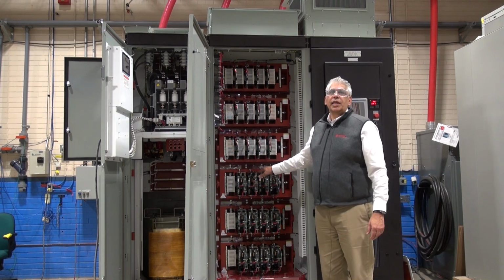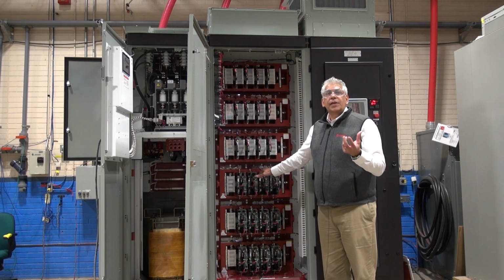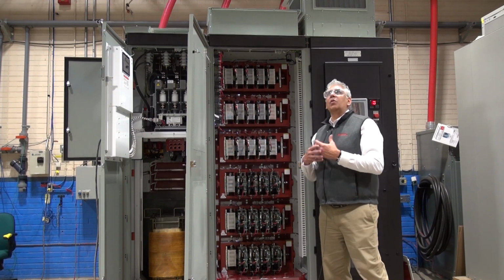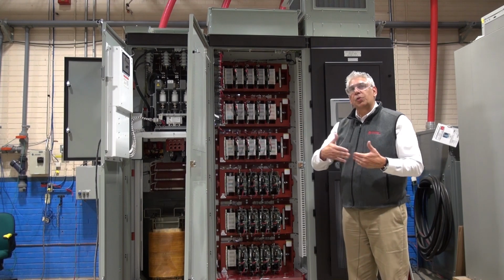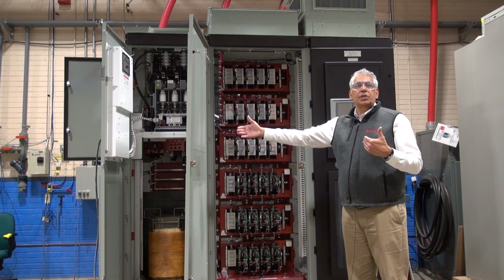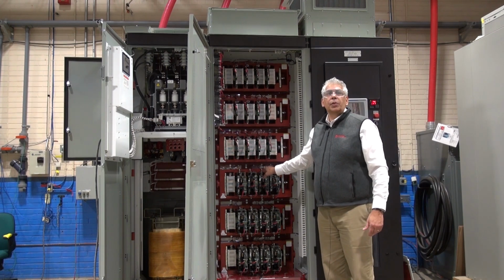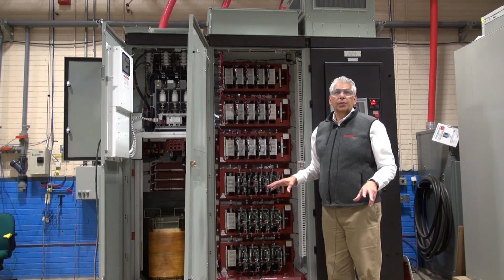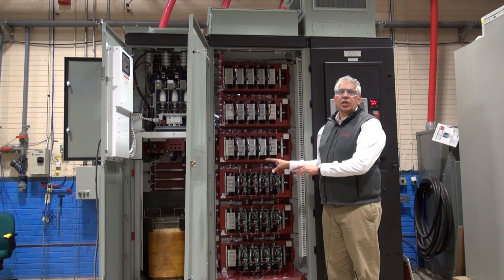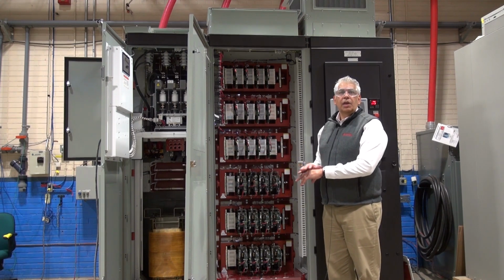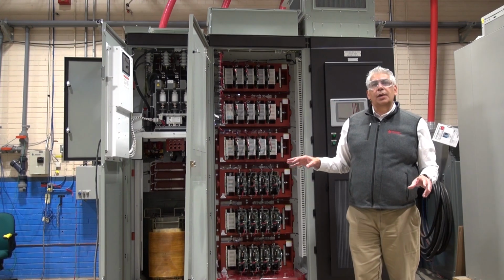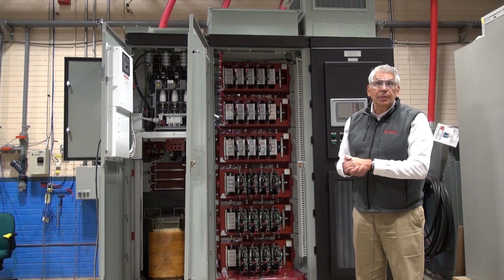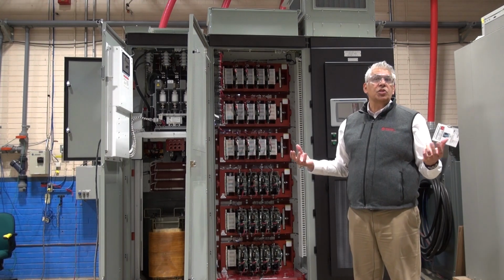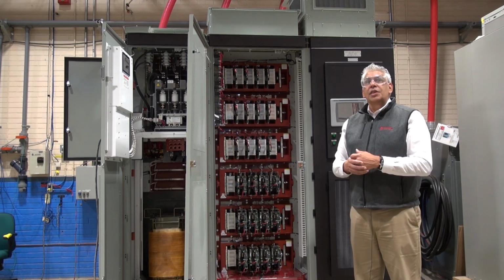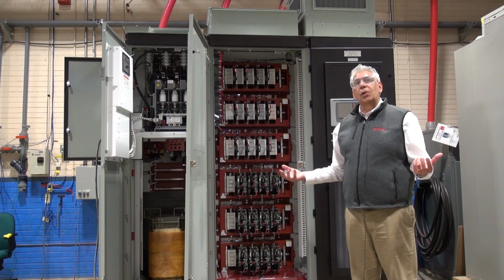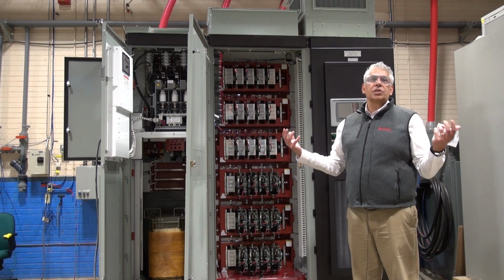The other big benefit with the SGCT is that it has a very low dV/dt rise time. If you think of low voltage drives, a lot of times the distance between the drive and the motor is very limited because of high rise times of the devices. This device features a 50 volt per microsecond rise time, which is exceedingly low in the marketplace. We operate these drives with motors up to 30 kilometers away from the drive, and we've got many applications up to that rating. Very popular for electrosubmersible pump applications, for subsea applications, or any applications, especially for mining, long overland conveyors. This provides you a tremendous amount of flexibility where you deploy the equipment to make it more cost effective from a system solution perspective.